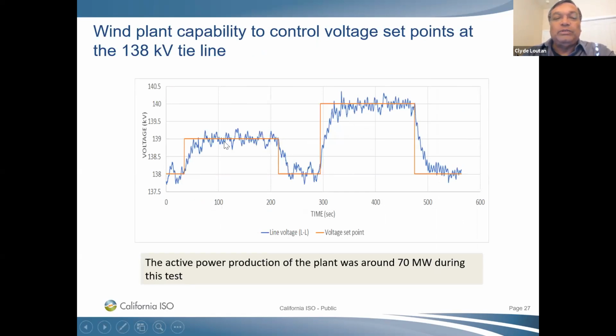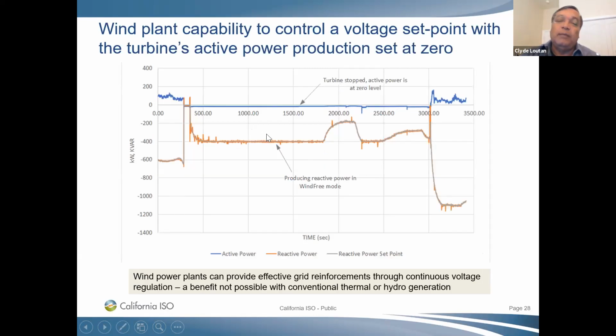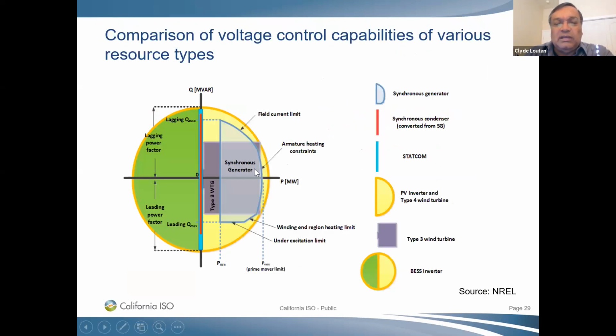Again, this here is looking at voltage, how well this wind plant can follow a voltage set point. We went over that in detail in the solar test, but at the end of this presentation, Jake's going to send out the slides so you guys can go back and look. And if you have any questions, always feel free to send me an email. So again, this is similar to operating the solar plant with no megawatt output. On this test here, the wind plant was basically sitting at 0, and you were able to control system voltage. So the beauty about this wind plant, or the newer wind plants coming in with plant controller, is that even though the wind is not blowing, so you have no megawatt output, these plants can provide reactive control to help you control the grid.